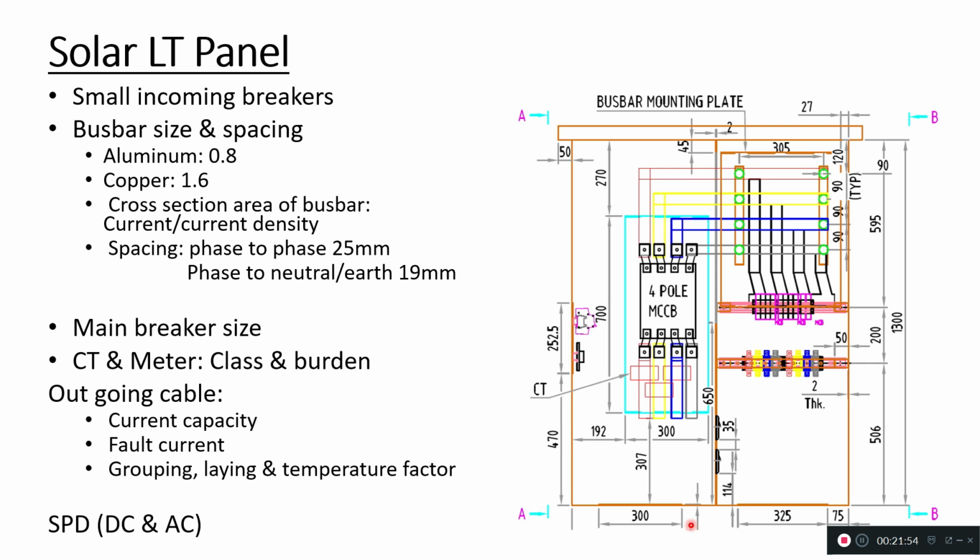It is very simple, and if you don't want to do the calculation, I have one more idea which is very easy for you to know the fault current. Whenever the client system is designed, it must have been designed with standard calculations. So if you see the breaker of the client in the panel where you are going to inject this solar power, you can see the fault current rating of that breaker, and you can use the same fault current rating for your breaker. The rating should be the same. This is one thumb rule which I follow sometimes, but it is better to cross check it.